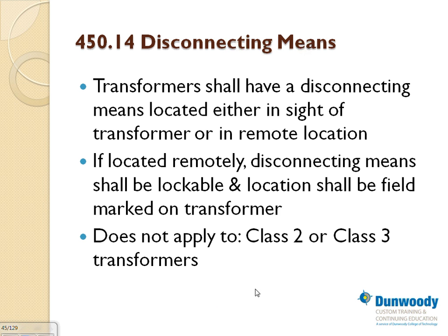Most of the time, guys, when you have a transformer, it is fed through a circuit breaker from a panel. So what they're talking about is this circuit breaker here: if it's not within sight of that transformer, then it has to be capable of being locked in the open position, and I have to put a nameplate right here that indicates the location of that circuit breaker. I think it's a good idea, right? If you get into a big plant and you walk around and there is a transformer, where is it fed from? You have to follow the conduit, right?